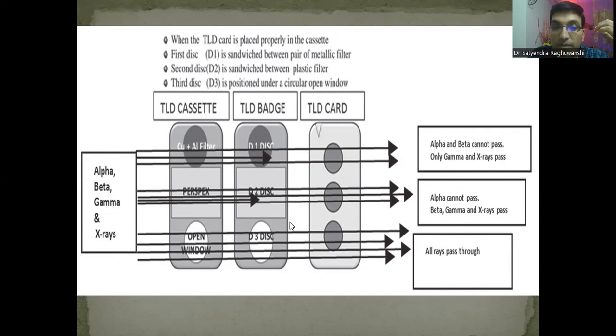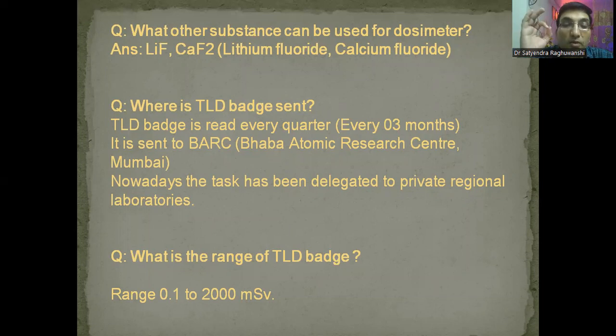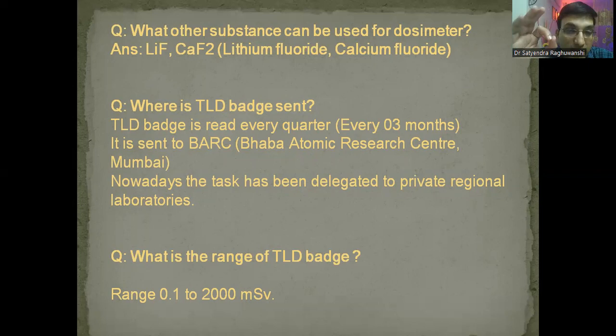How does the TLD badge work? Through the open window, all alpha, beta, gamma, and x-rays pass — registered by disc three. Through the plastic window, alpha rays cannot pass; beta, gamma, and x-rays pass. Through the metal filter (copper and aluminum), alpha and beta cannot pass — only gamma and x-rays pass. By measuring the exposure in the three discs, we determine what kind of radiation the person has been exposed to. The range of the TLD badge is 0.1 to 2000 millisieverts.